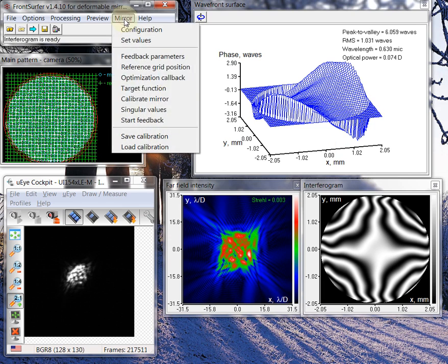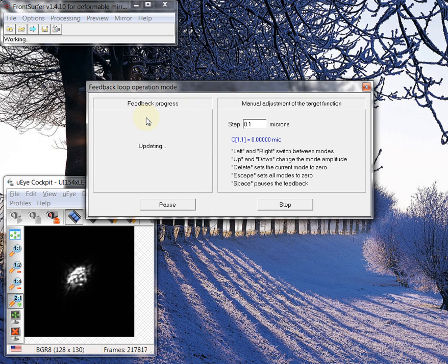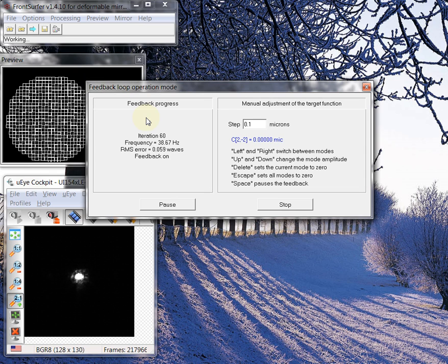Let's try to create some other aberrations. I reset it again. Another astigmatism, in the orthogonal direction. Yeah, let's try to make coma. It's Zernike polynomial 3.1. Yeah, it's a very good coma. So just coma, let's stop it.